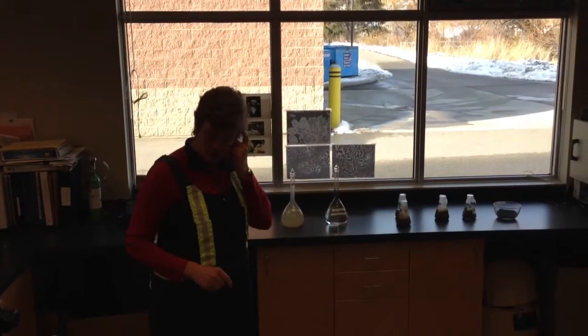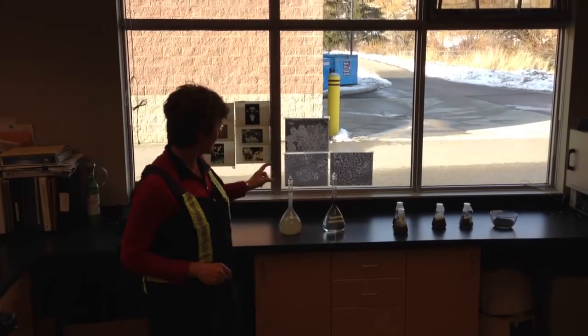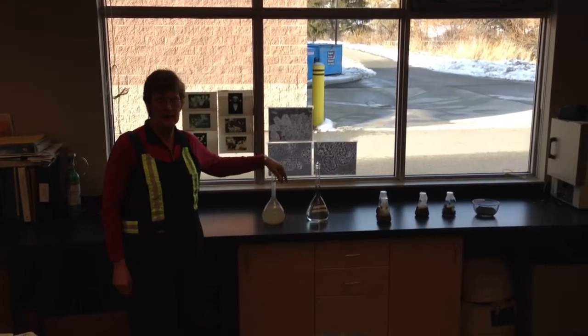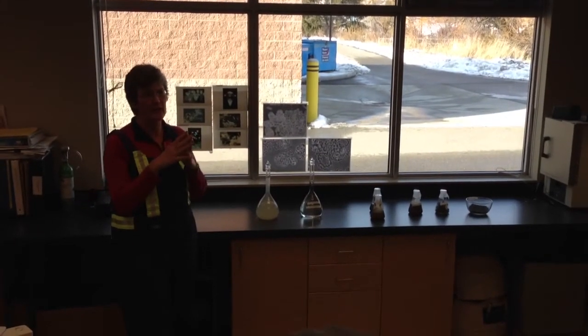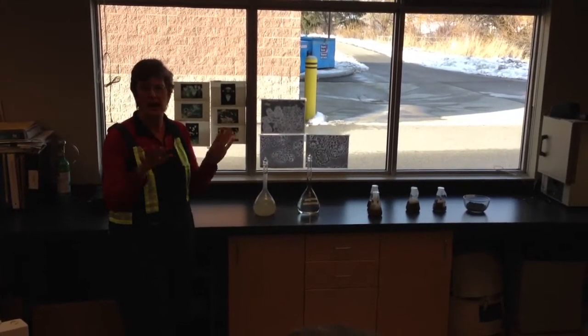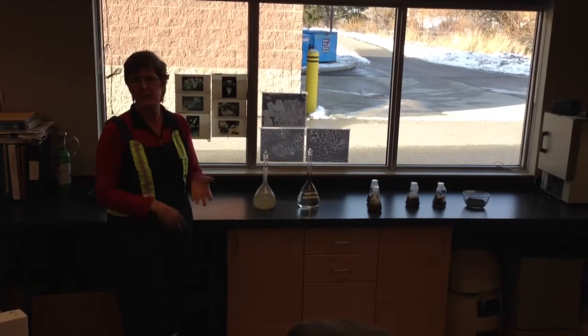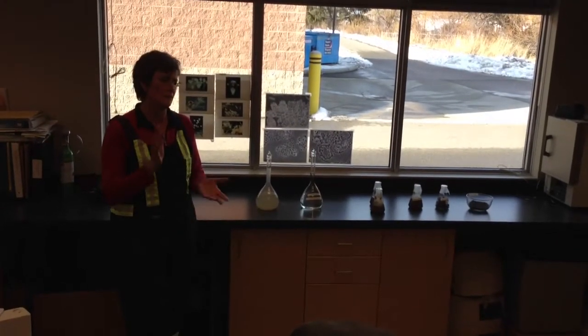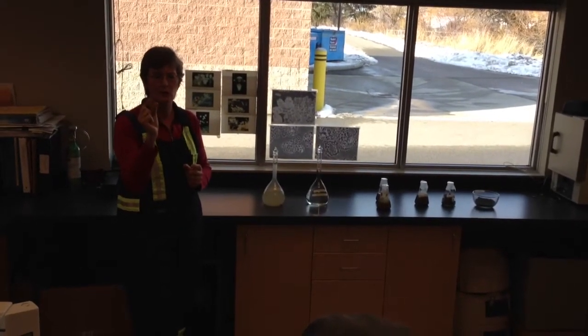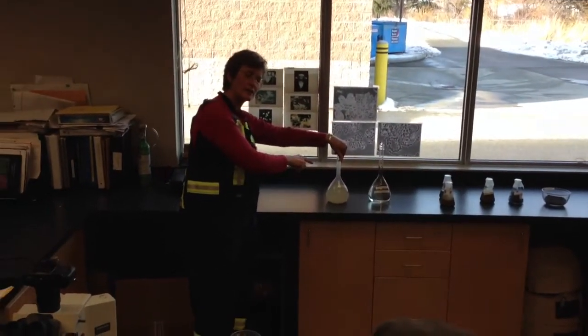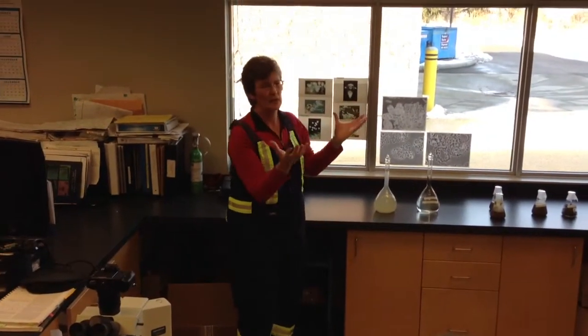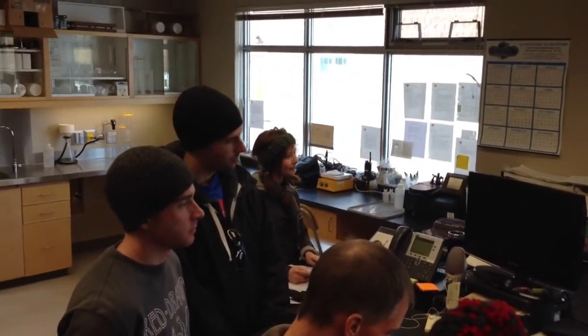As we go through the plant, we'll start at the beginning. The first stage is to screen. We take the coarse solids out. We have fine screens that will mechanically remove the sticks, the rags, as much as won't fit through the small screens. This is after that stage. So we could have something coming in that the bacteria wouldn't be able to consume. So that's removed at the first stage at the headworks.